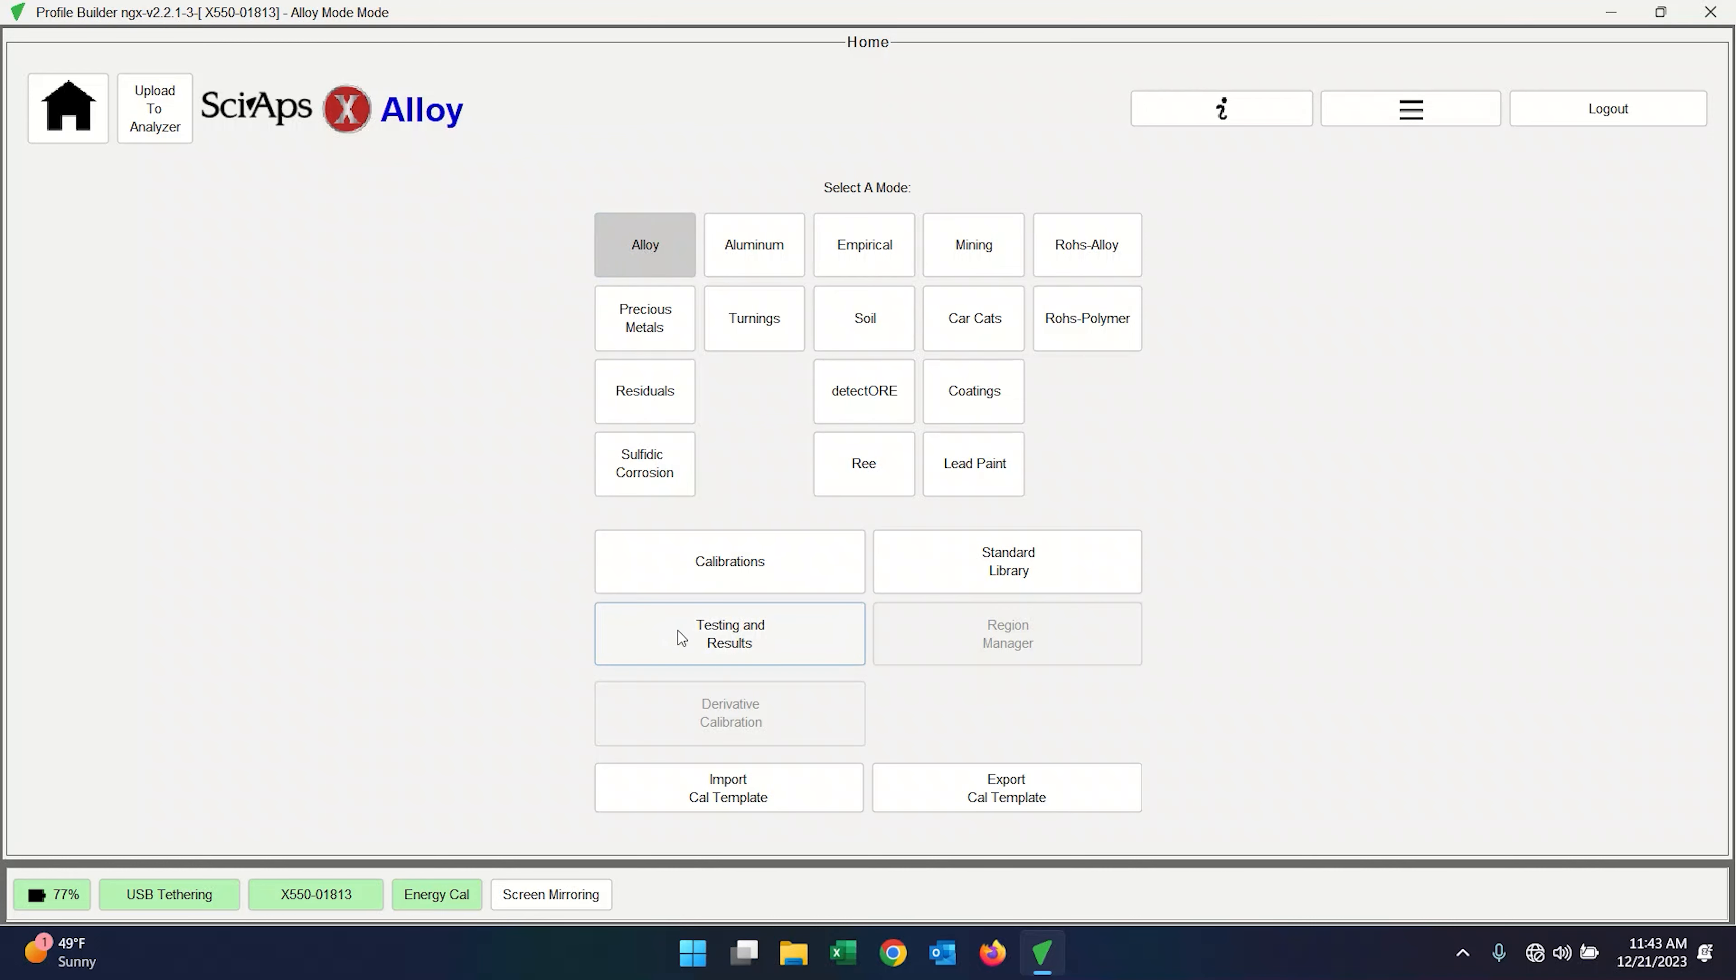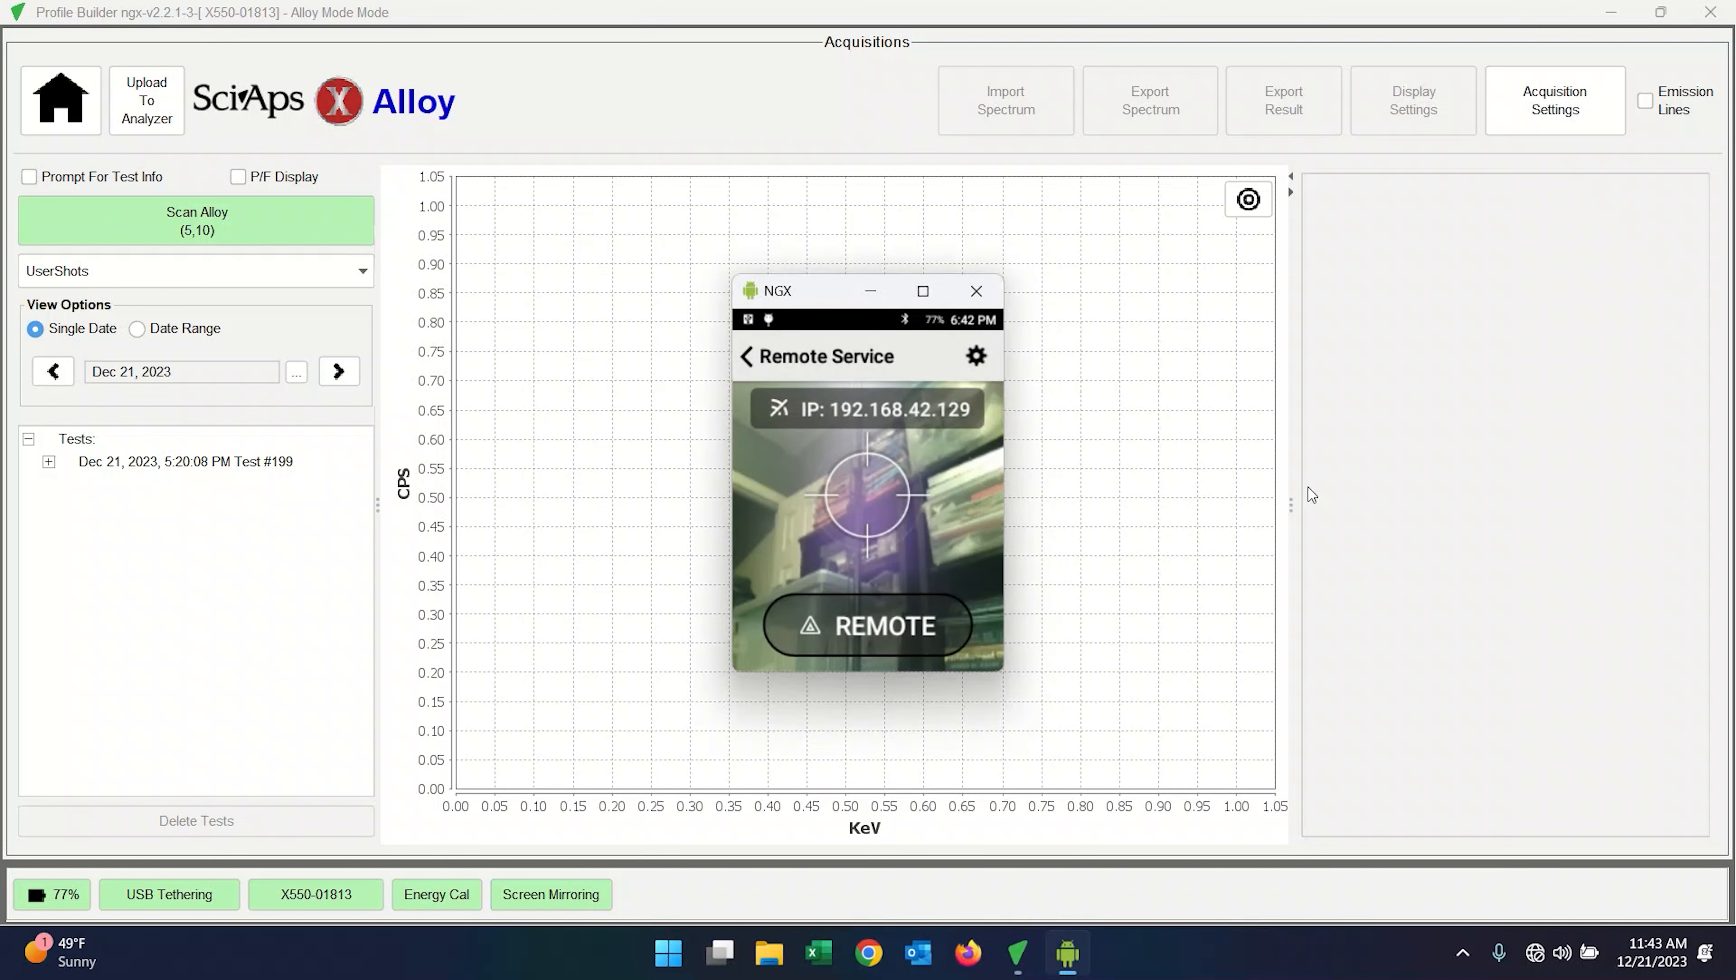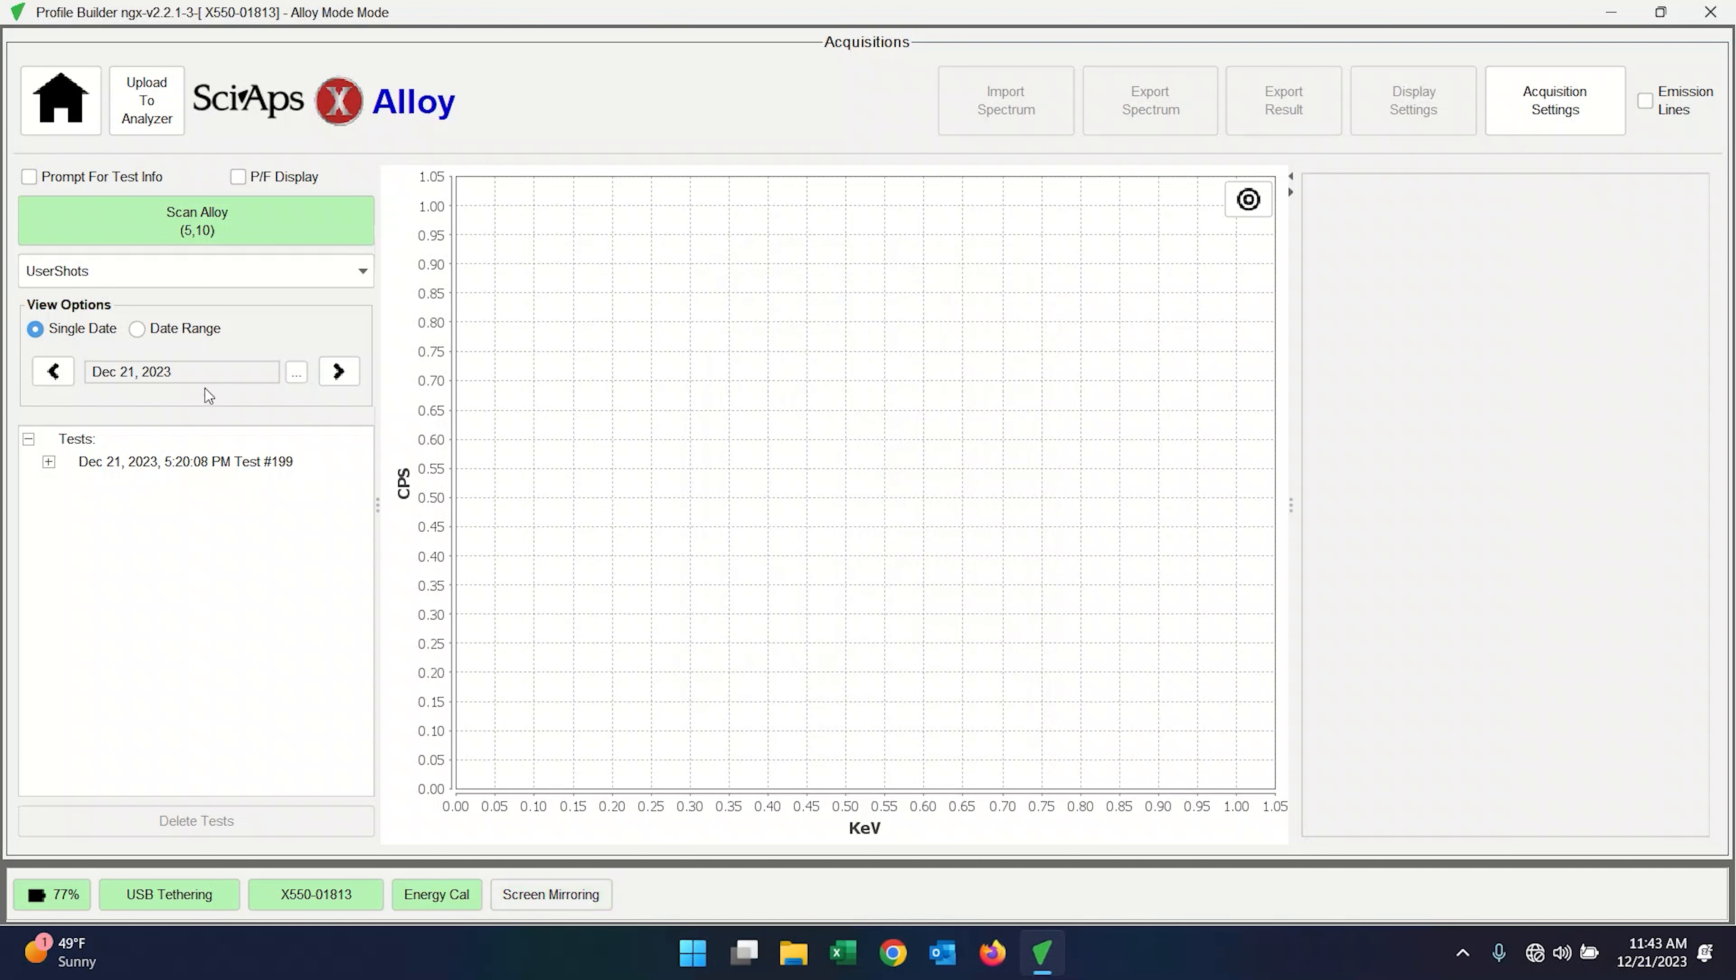So you'll see there's a mode that we're in here. I'm going to select, keep the alloy selected. We're not doing a lead paint or precious metals or anything. We're just doing basically alloy mode. And then we want to see testing and results. So I'm going to click that. Now, if you want to mirror your screen, like what I did on the video, on the bottom, you see that little white box mirror screen or screen mirroring, excuse me, you can click that. And then you can see my bookshelf storage racks next door here on the camera. But that'll let you totally run the instrument from your computer, which I think is great.